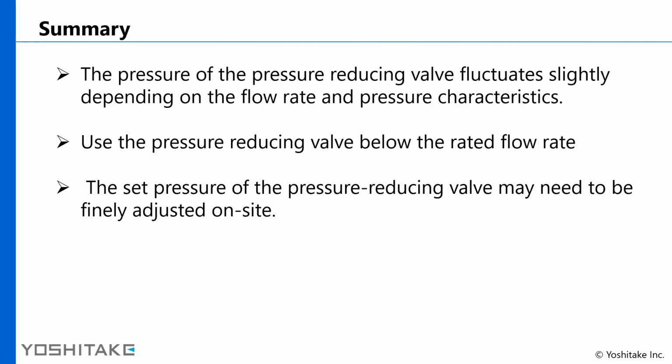This is a summary of the pressure reducing valve. The reduced pressure fluctuates slightly depending on the flow rate and inlet pressure. Use the pressure reducing valve below the rated flow rate. The set pressure of the pressure reducing valve may need to be finely adjusted on site.